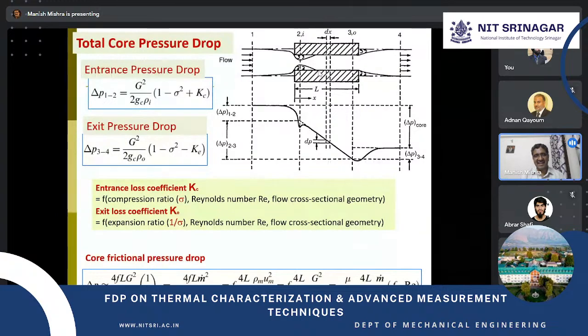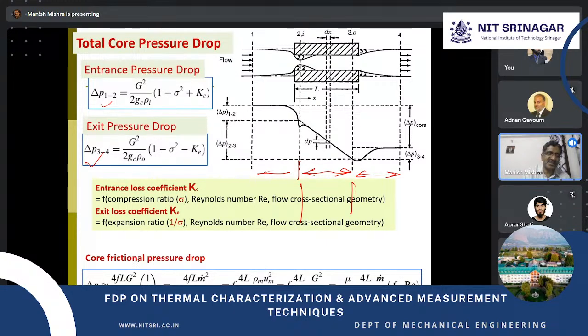Now, pressure drop. Like heat transfer, we calculate the pressure drop, and the friction coefficient F that comes from it is also a tricky issue. Suppose this is the heat exchanger core: the pressure drop doesn't only take place here, but also at the entry header and the exit header, where sudden contraction and sudden expansion take place. If I sum up all these things, there are so many components: between points 1 to 2 there's one pressure drop, between 3 to 4 another, and between 2 to 3 the normal pressure drop. That normal pressure drop itself is not that simple.